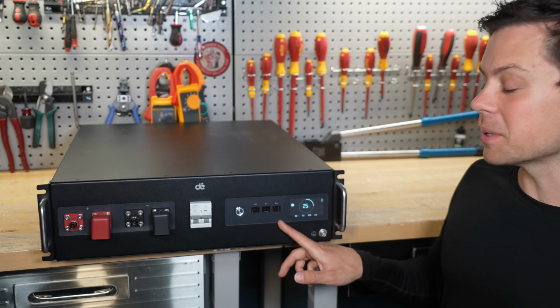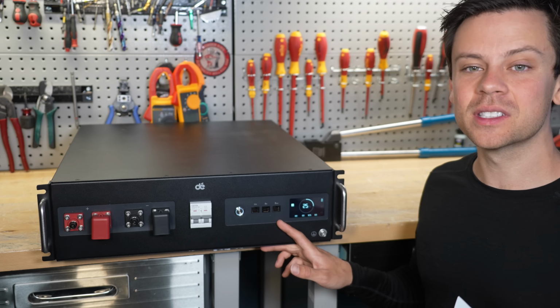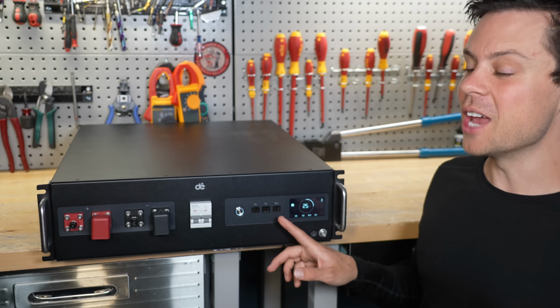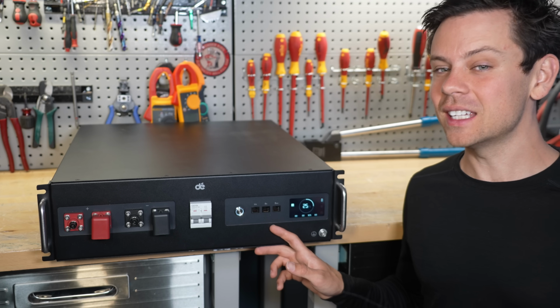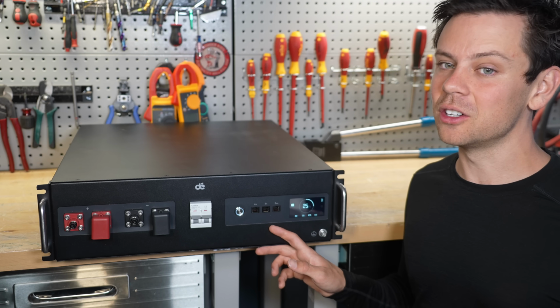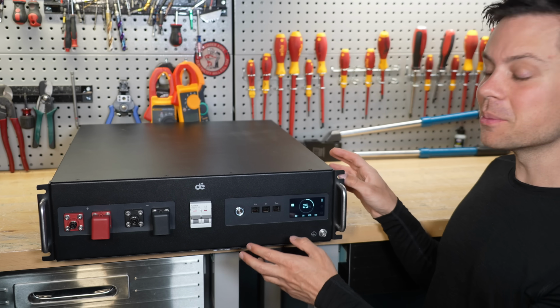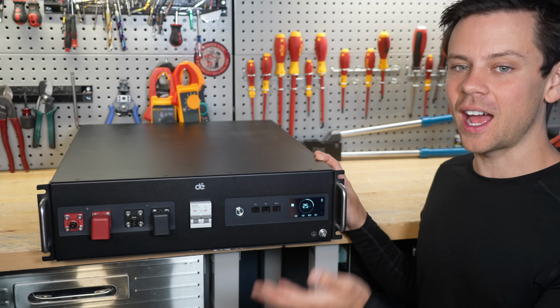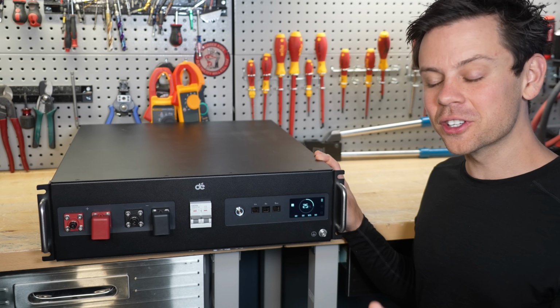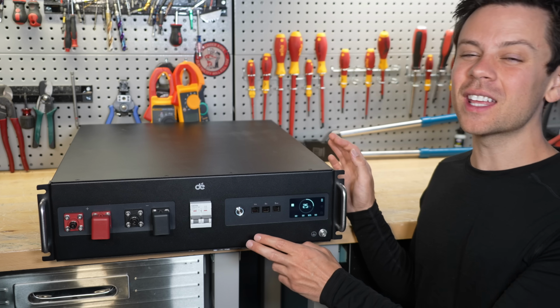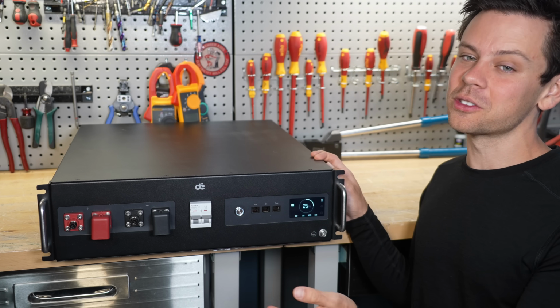That's because this BMS has a coulometer and uses that to cycle instead of voltage. It will use the voltage thresholds if it needs to, but usually it's going to cycle with the coulometer. Nowadays most of the older manufacturers don't have this issue, and they pull 100 to 101. But if you take the cells out and test them, they're about 106.